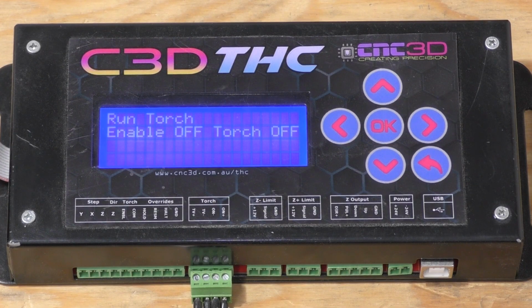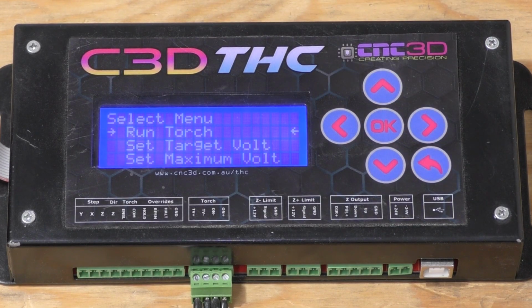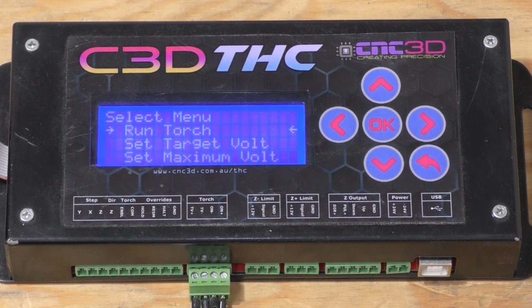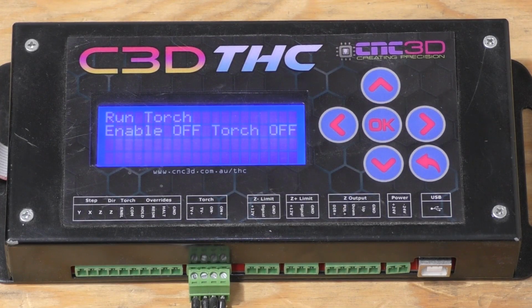If you are in any other menu other than the Run Torch menu, the THC will not actually do anything. It's basically just in a configuration mode at that point in time. So just keep in mind that you always want to return back to the Run Torch menu. We're going to use the back button here to take you into the main menu. You can see that the very top menu here is the actual Run Torch menu. After you've done all of your settings changes, just go back in there, and that will allow you to start operating your C3D THC.